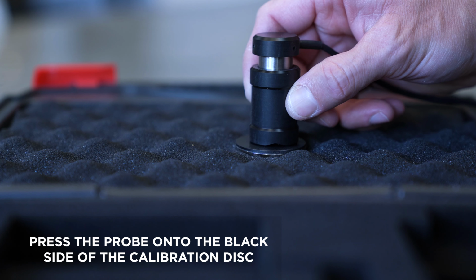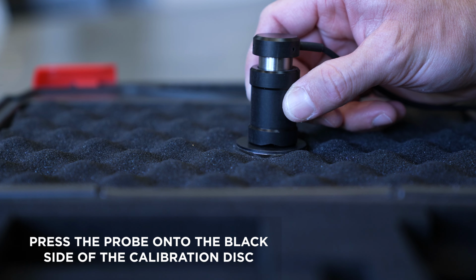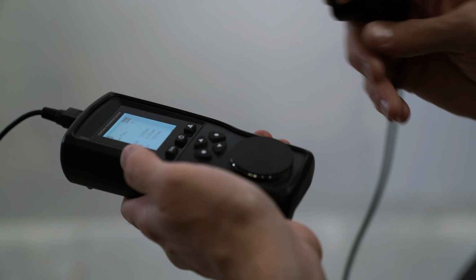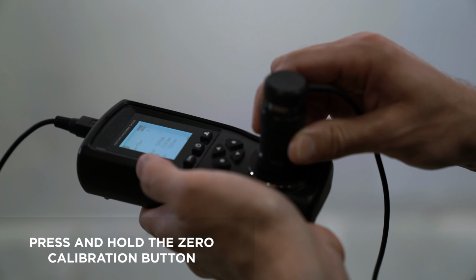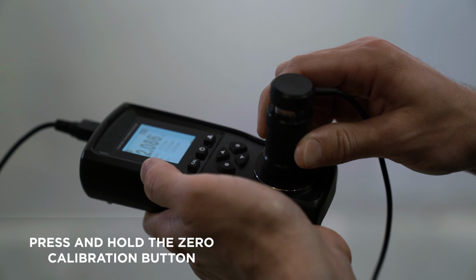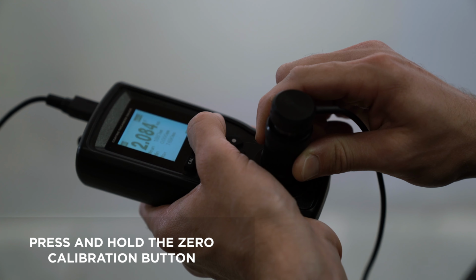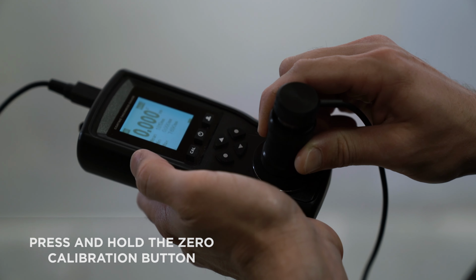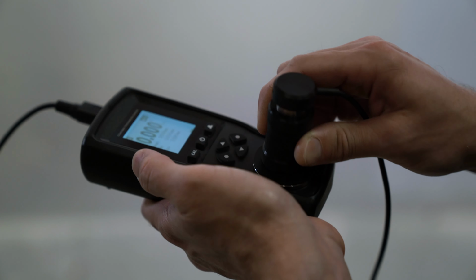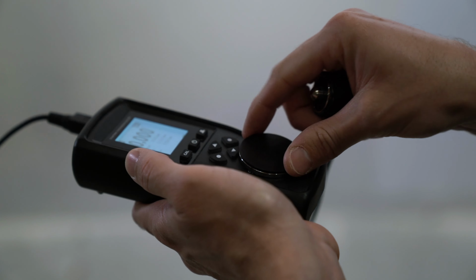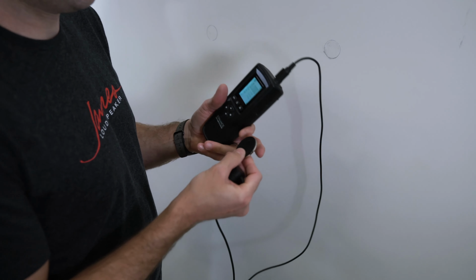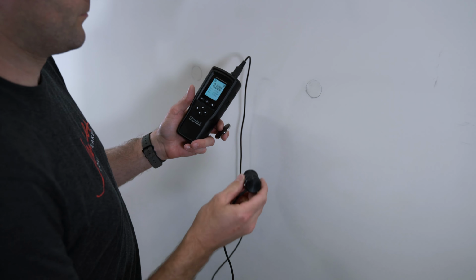Press the probe onto the black side of the calibration disc, ensuring that you are holding the probe by the collar only. While pressing the probe against the disc, press and hold the zero calibration button. Initially, you will hear a single beep, followed by 2 additional beeps. The display should now read 0 millimeters with the word 0 flashing below.